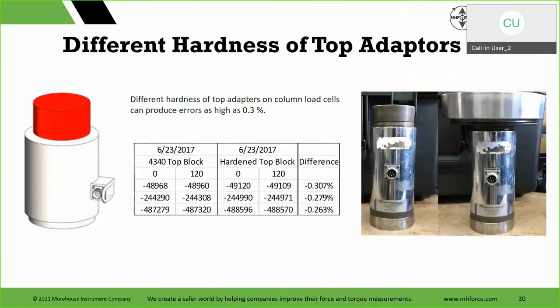Different hardness of top adapters, mentioned it earlier, produce error as high as 0.3%. This is an example of 0.3. Here you have it. All I'm talking about, same load cell here, really old load cell, single column cell. Same base plate, just varying the hardness of that top adapter, and you can see a 0.307 difference. This was done the same day.